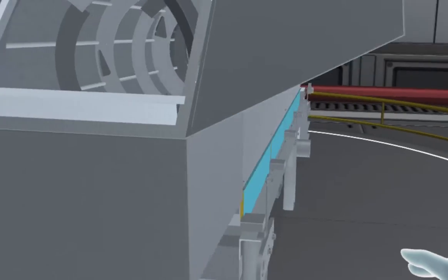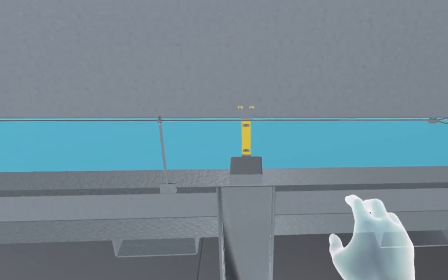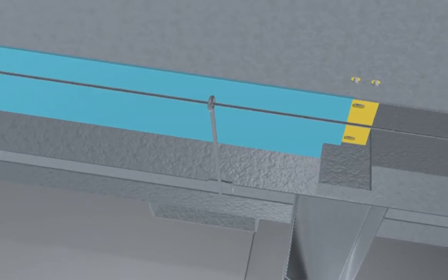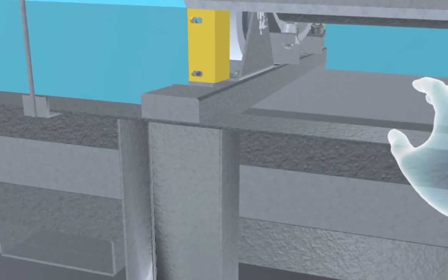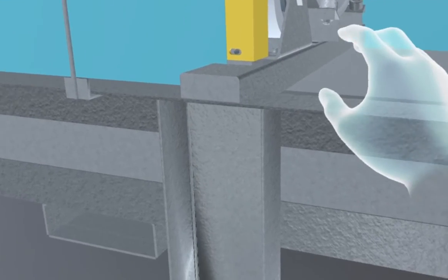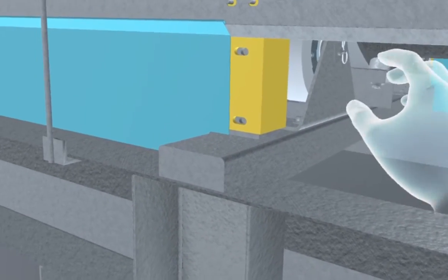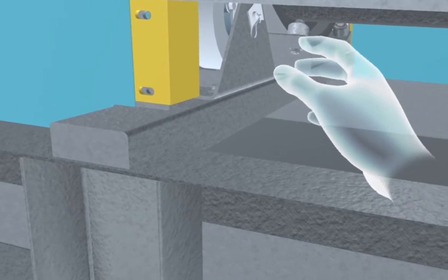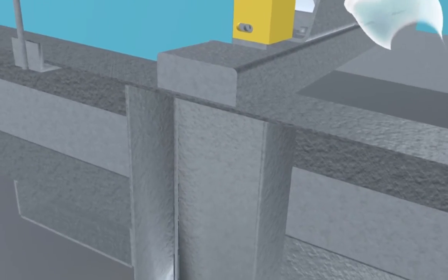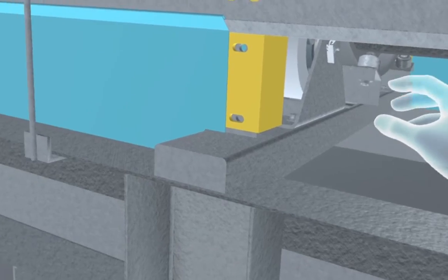And the last part we want to talk about here on the RDT is really the access points you're going to use the most often. And that's these little removable panels here on the side. So you can go in, and they're just removable by hand, then they lift off with a little lip here, and you can set them down. And then now you can see inside the drum. There's two things really that you need to see here. One is the trunnion wheels that we discussed a little earlier. These are in a wetted area, and they're run on bearings. So those bearings need grease. So we have Zerk fittings put on each one of them, and they can be accessed through removing these side panels to be greased.